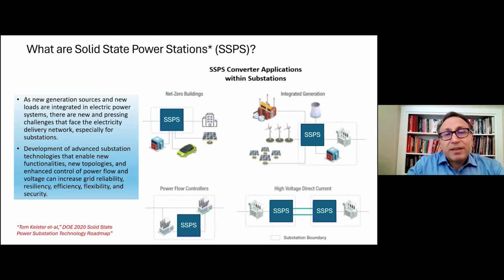There's a new topic that has been initiated by modernization of the grid, and that is the solid state power substation. In the old or conventional power system, there were few power generators, and there was a transmission line transferring the power to the load centers. But in new grids we see a lot of new loads and a lot of new generation sources, such as PV, wind turbine, and hydrogen, that have been distributed along the grid.